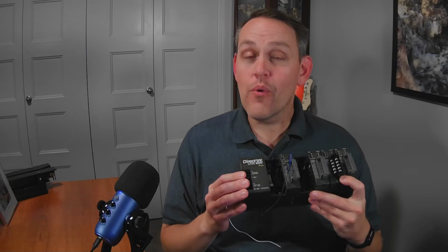But I've got two sensors that need to show the air gates are closed. Now, the simple way is to simply wire in those two sensors real quick and tape a washer to the head. The sensors are on now. Or I could just go into the input and tell it, you know what, those two sensors where they communicate, it's always on. Might not even have wires hooked up to it, but it's always on.